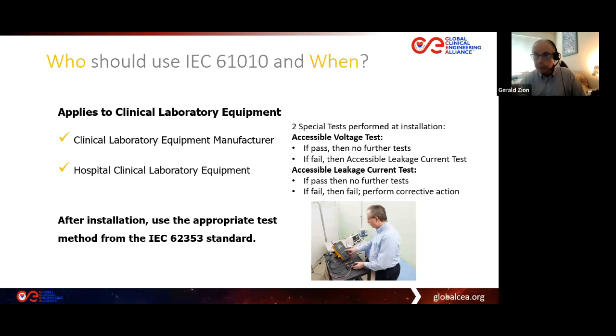After installation, after go live, we as biomedical engineers and field service engineers are advised by the IEC committees to use the IEC 62353 standard, with whatever the appropriate test method may be for that. Okay, so for what we are going to do as biomedical engineers, it is 62353 after go live, but the manufacturer is responsible for using 61010 and these two particular tests and documenting the results for us before we go live.